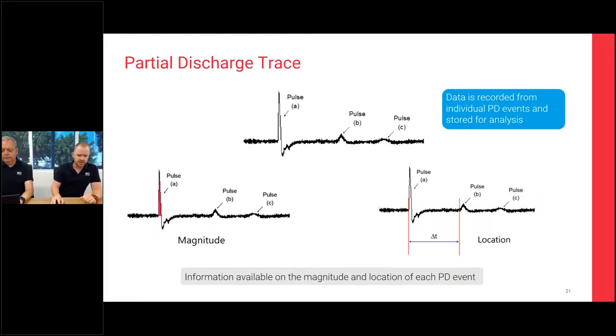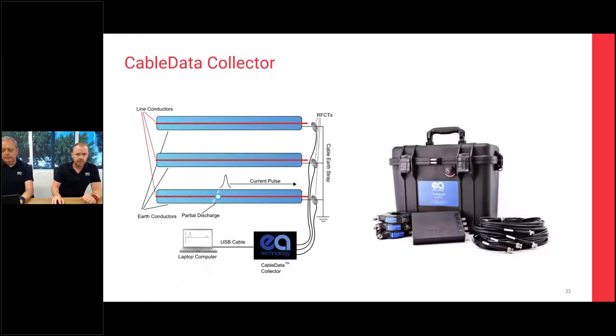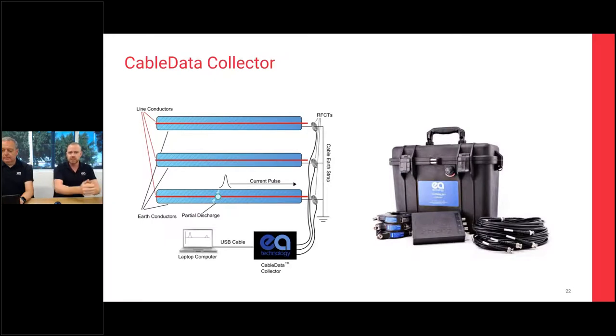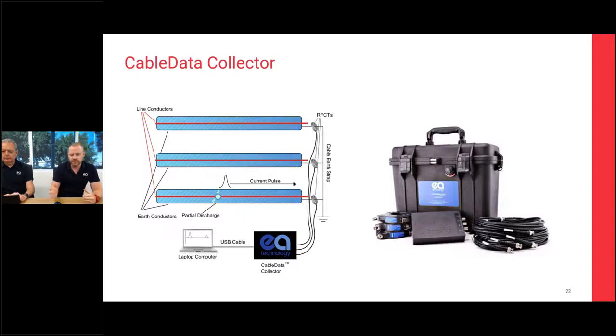The main piece of instrumentation is the cable data collector. You have a piece of hardware, three RFCTs connected by leads to a laptop running software where you enter who you are, where you are, what you're testing, and importantly the length of the cable if known. Once you start the software, it takes about 7–10 minutes to capture the cable PD signals bouncing up and down the cables. Then you can move on to the next set of cables and map your network out. It's best to test all your cables from both ends if possible. The data is then analysed offsite.